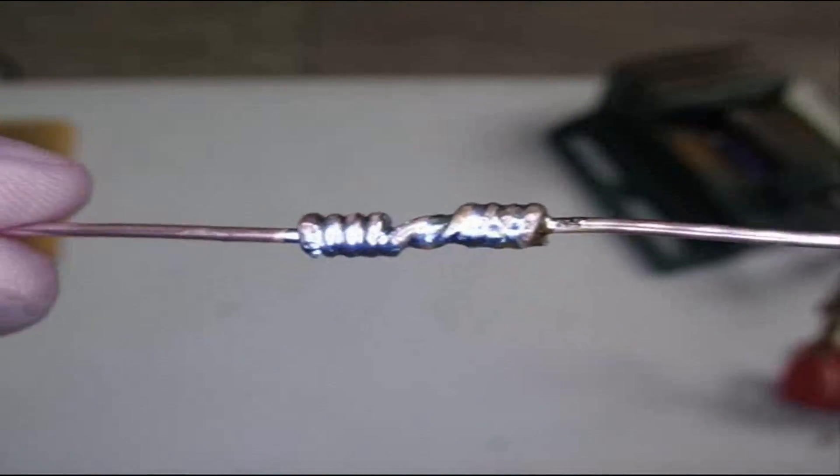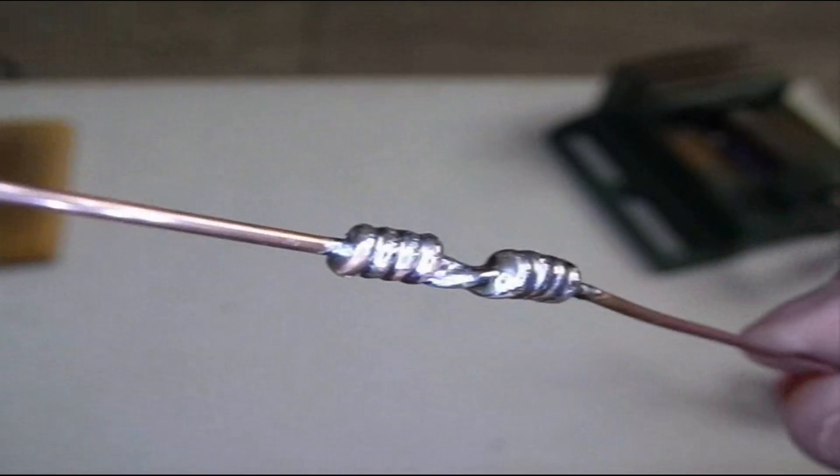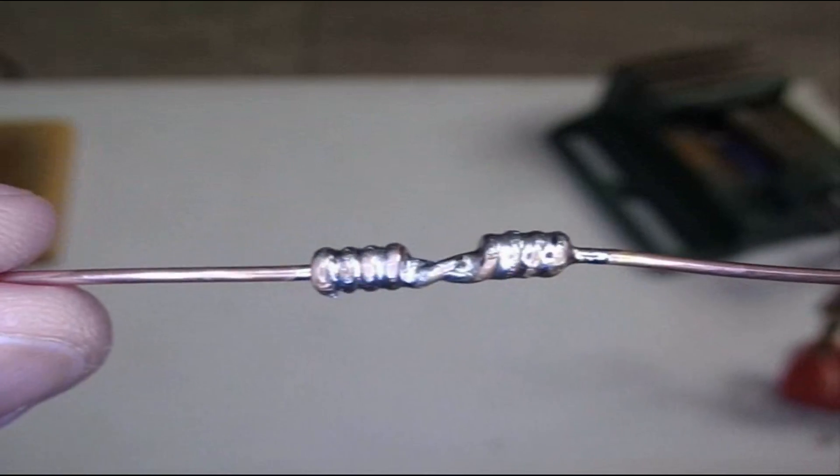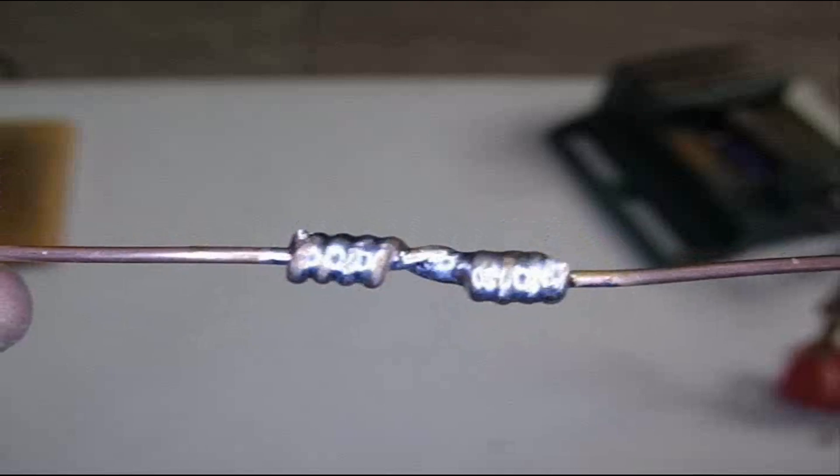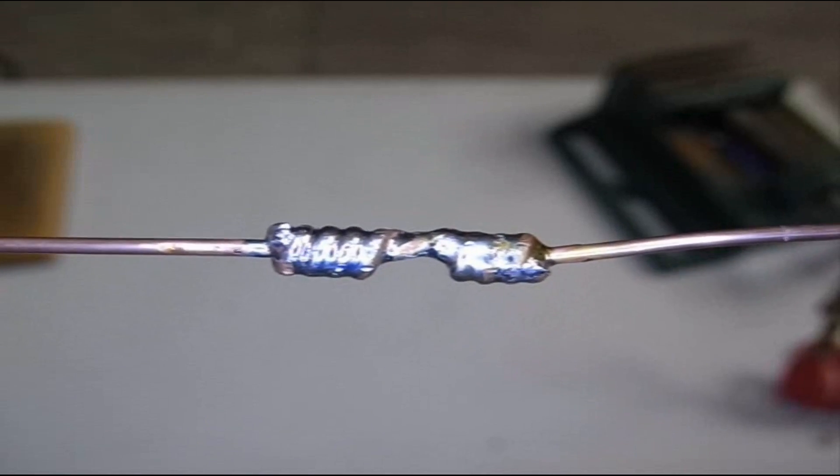So here's our joint. And we're soldered through the ends. Yes we've got good penetration of solder throughout the joint. And that will be tremendously strong. It will easily support the pull of the wire and be about as strong as the wire itself.